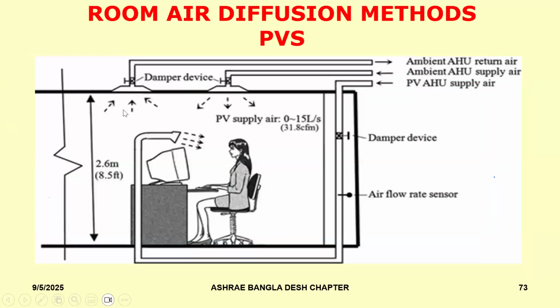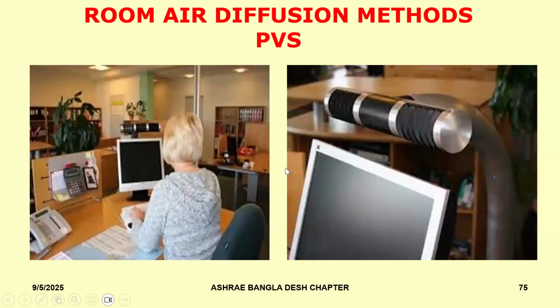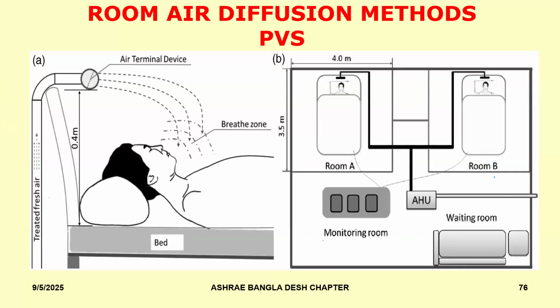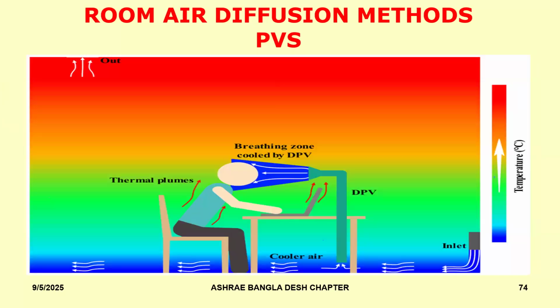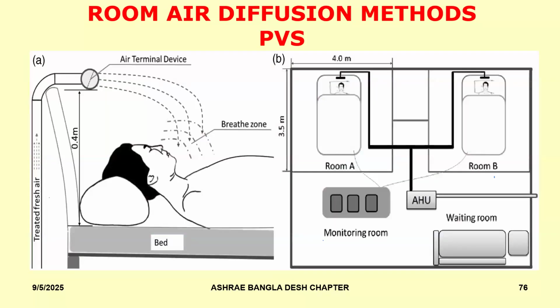Or you could also look at, instead of using outlets like this, radiant ceiling panels. So that's another way of taking care of the heat from the room and providing outdoor air directly for breathing purposes. So this can also be applied in healthcare environments. You can imagine that when we are doing this, the actual amount of outdoor air that we require will be much, much less. That's why I said you can have an effectiveness of something like 1.6 or 1.7. So you really require only about 20 to 30% of the outdoor air as you would in a normal case. So this is slowly getting traction now, and people are paying attention to personalized ventilation systems.